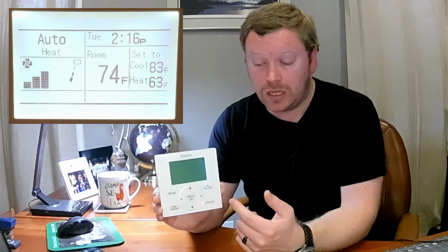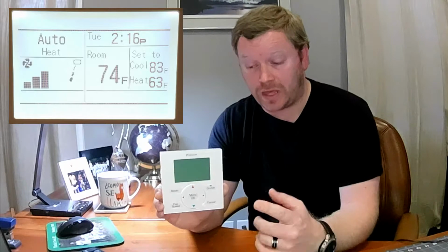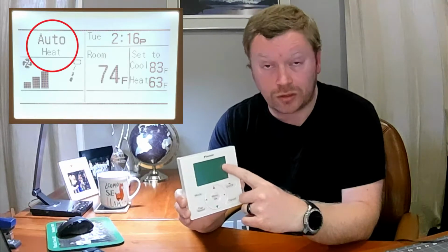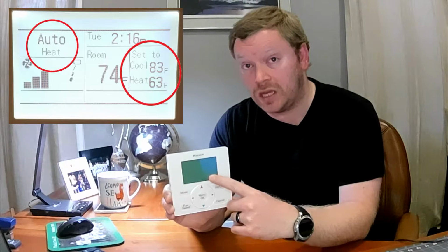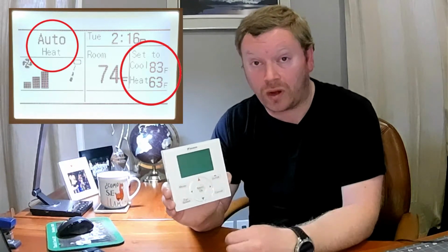The only time you're going to be able to see both the heating and cooling set points displayed on the nav at the same time is if you are at the master and the master is in auto, and if you're using dual set points. So out of the box, if you haven't changed anything, then when you put it in auto, you'll have your heat and your cool set point displayed on the right hand side, and you can toggle between them with the left and right arrows. And once you've highlighted which set point you want changed, you just hit the up and down arrows to change that set point. But most of the time, if you're not in auto, you're either going to be in heating or cooling.